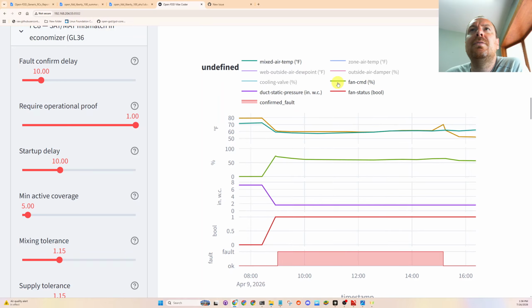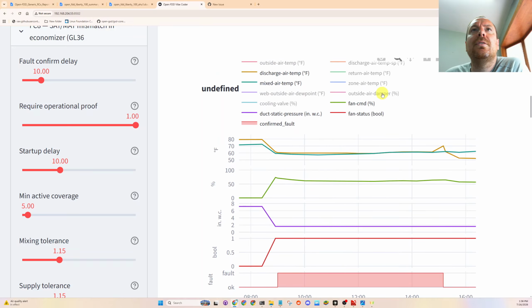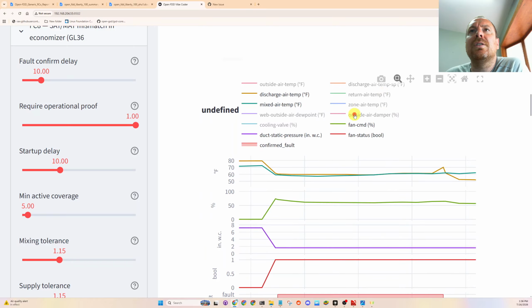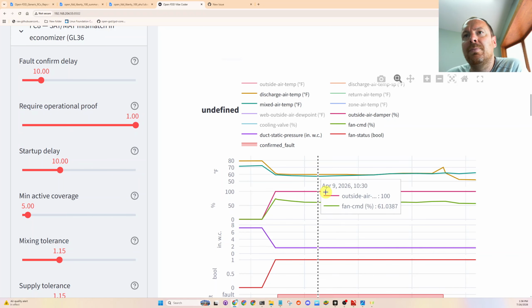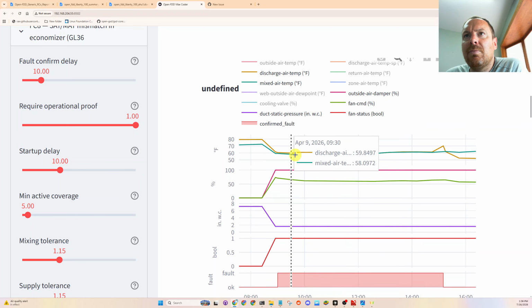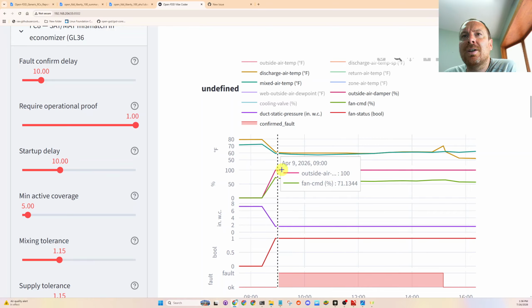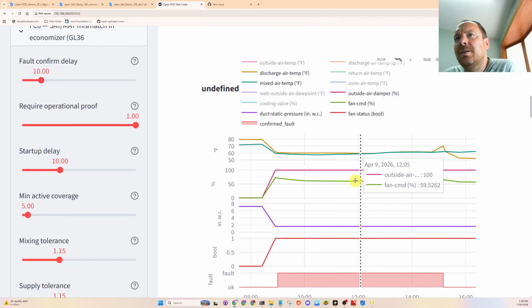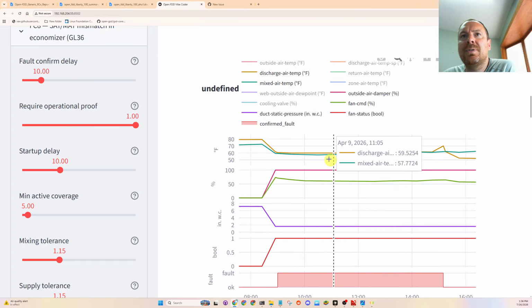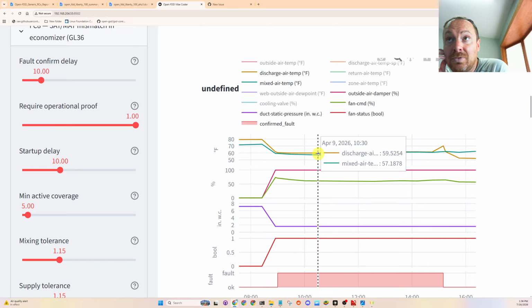Where is our outside damper? Ooh, 100% open. Nice, so this is perfect. This is exactly what we'd want to look for, that we're in 100% outside air mode. Duct static pressure is maintained at 59% fan speed, and we have 100% free cooling going on right there.